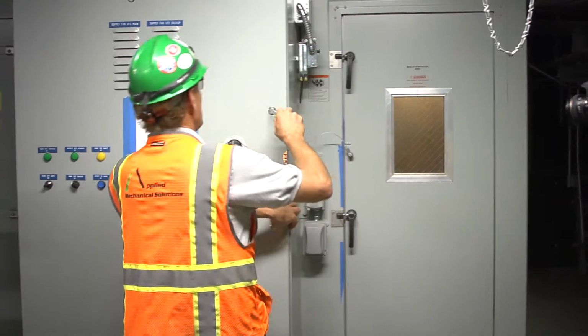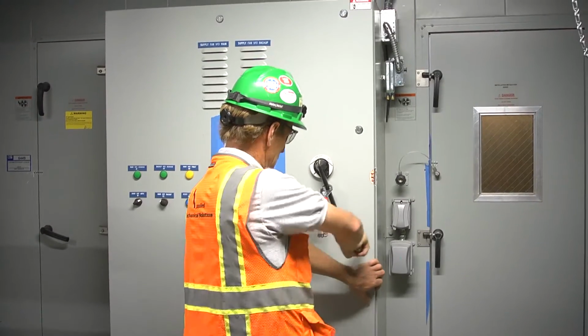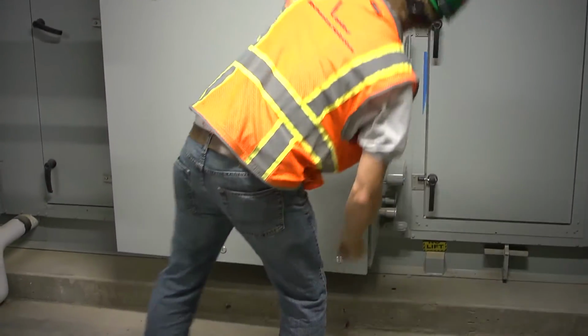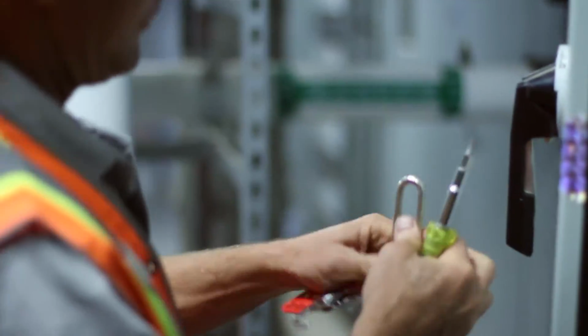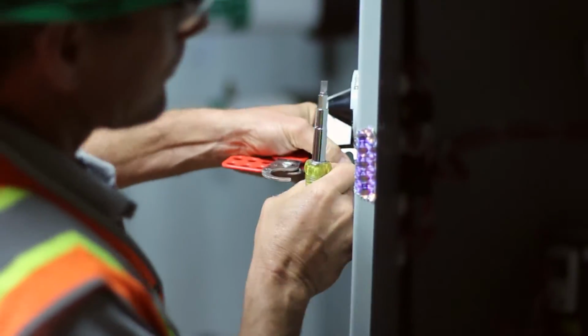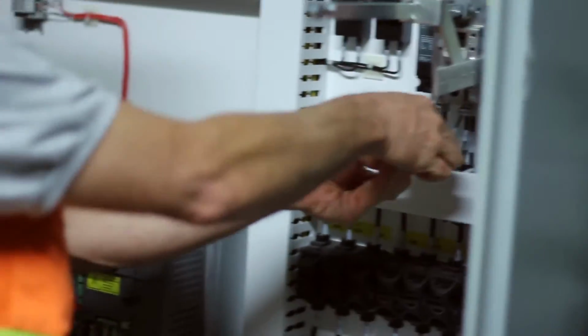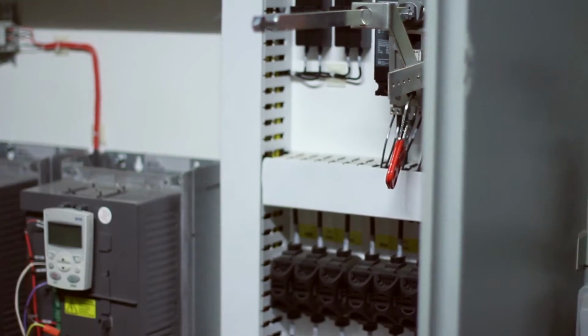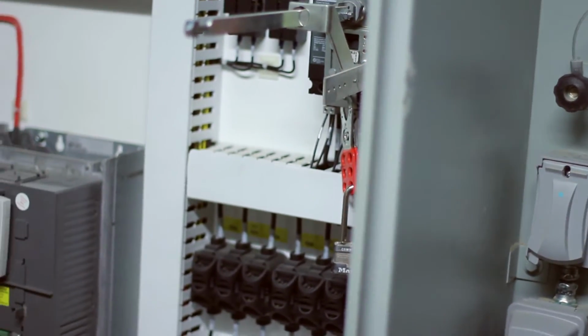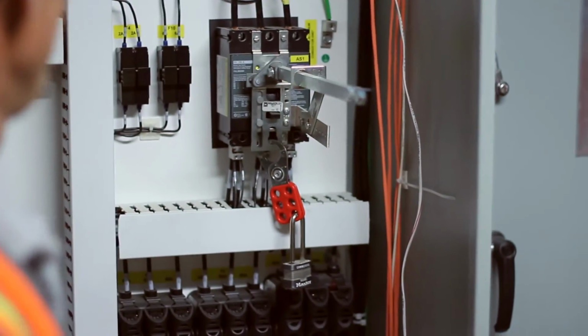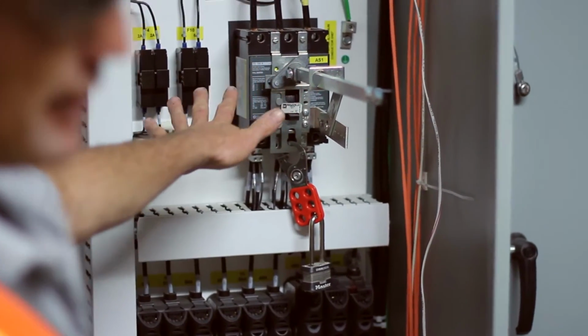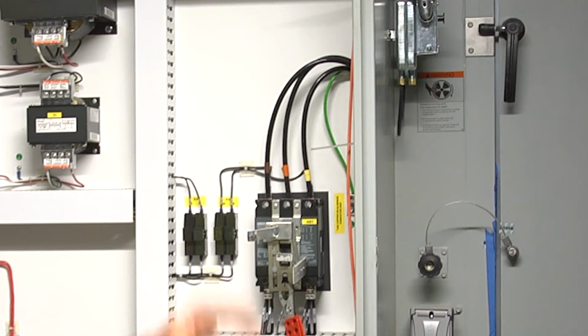So at this point, we can open up the door here. There we go. Once we have it off, we can actually lock it out right here, again inside the unit. And the unit could be worked on here with a lockout right on this. So line side voltage comes in here on the top, and the load side is below that on the molded case switch. This is not a circuit breaker, this is a molded case switch. So your circuit protection's all within the fuses, circuit breakers, and then building site safe lineup.